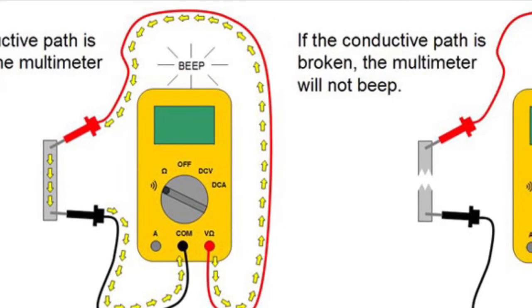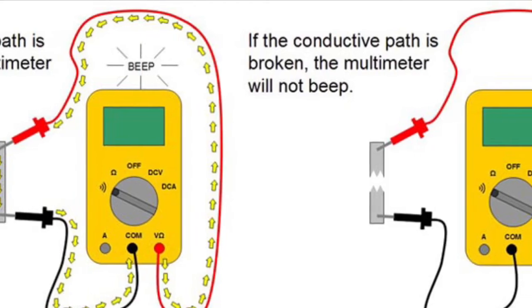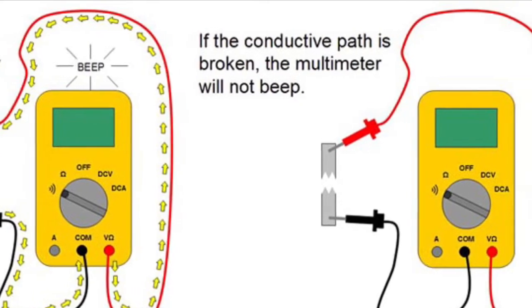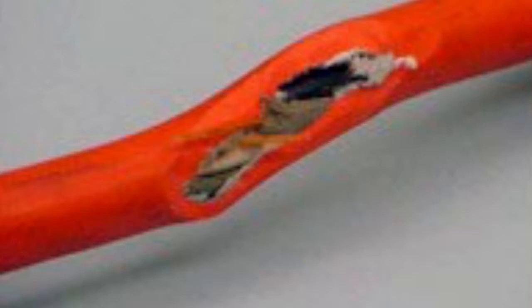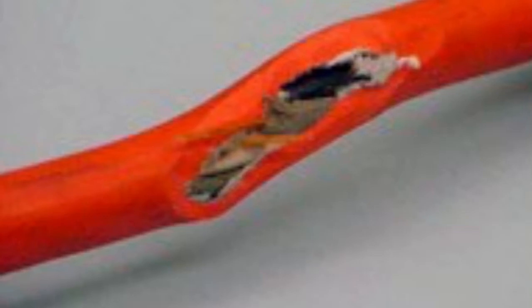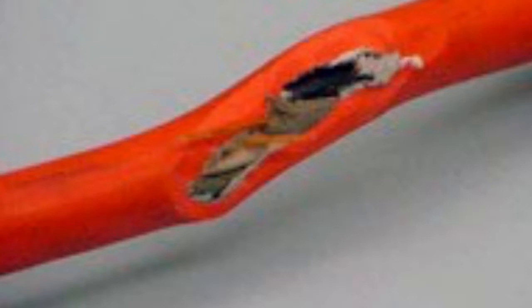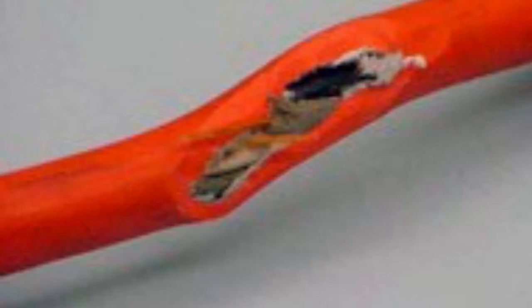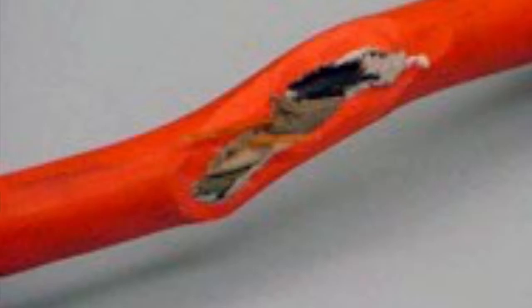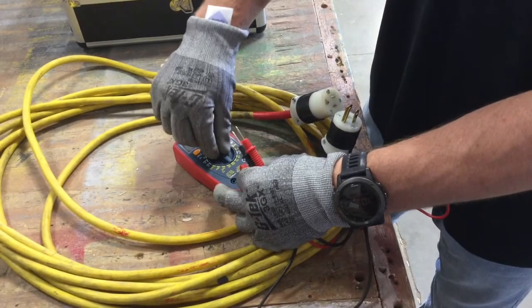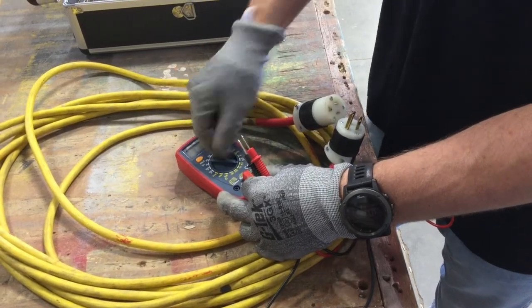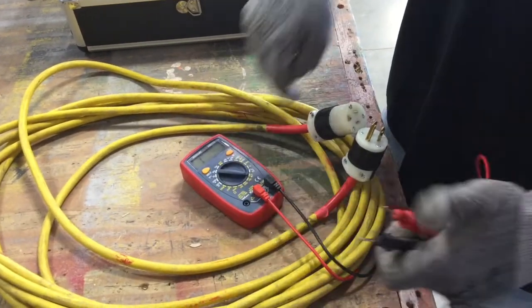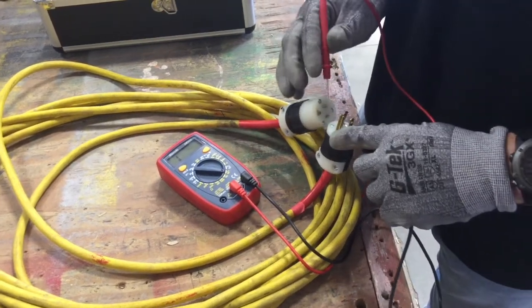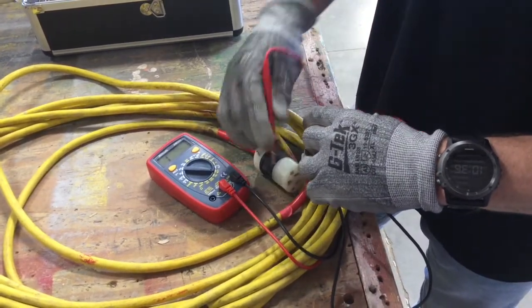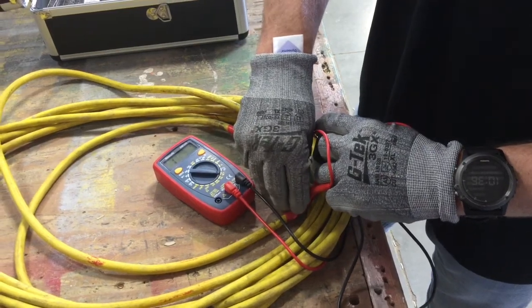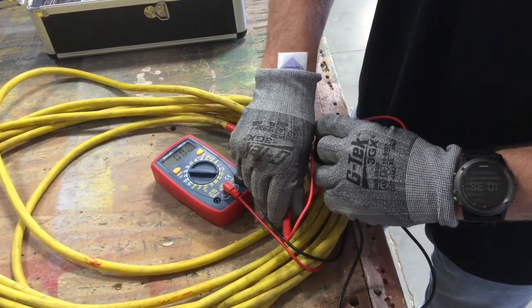To test extension cords and equipment, use a multimeter. If the conductive path is broken, the multimeter will not beep or read something other than 0. Visually inspect extension cords for external defects such as deformed or missing prongs, insulating damage, indications of possible internal damage, cracked or cut jackets, loose or bent prongs, and melted cord caps. Test grounding conductors on male and female ends of cords for continuity by using a multimeter on the ohm setting. There should be continuity. The multimeter should beep and read 0. Test the grounding conductor on either end of the cord for continuity with the hot and neutral conductors. There should be no continuity.